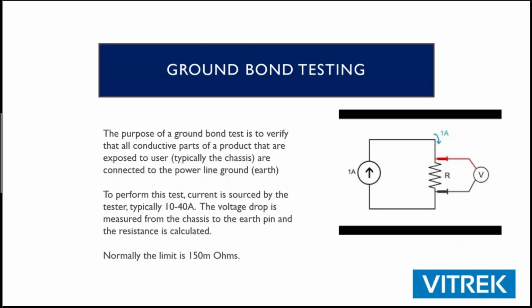So the other major component here is ground bond testing or ground continuity testing. They're very similar in the way that they work. What you're trying to do is verify that you have a low resistance path from your earth ground pin to the chassis of your product. In the event that you had mains breakdown to the chassis, you want the current path to be of low resistance, so all of that current can return back and trip a circuit breaker.